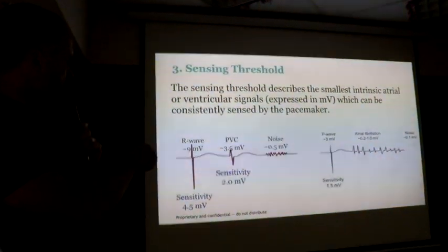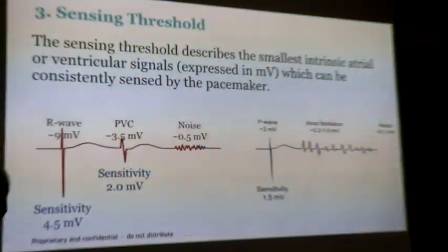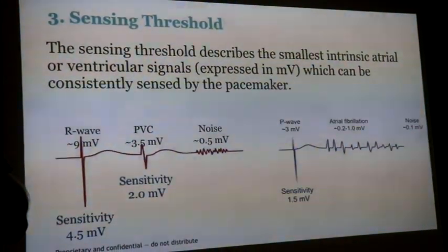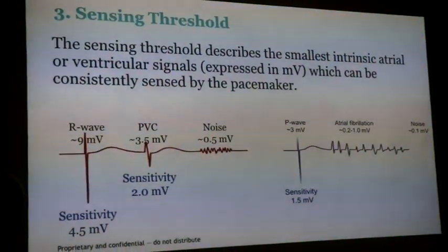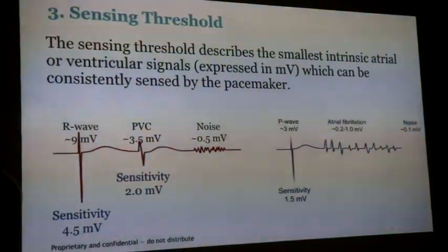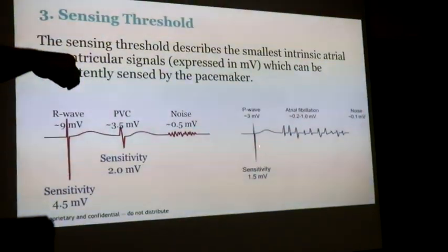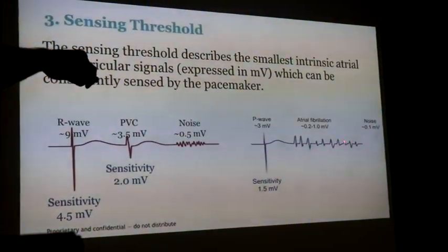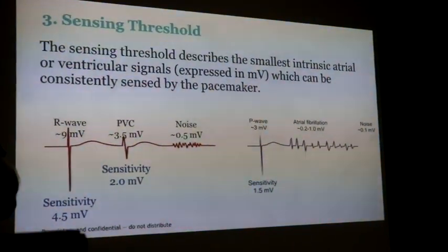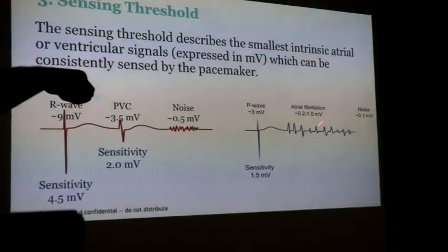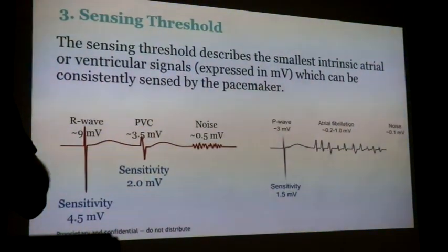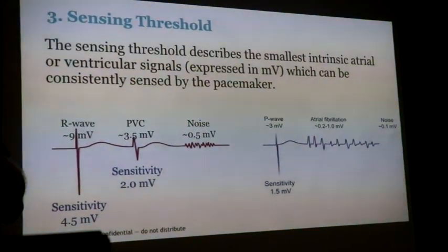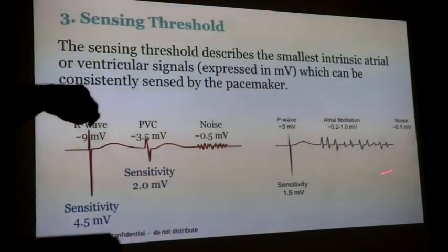So, sensing threshold. Normally we'd set the sensing threshold at around 2.5 millivolts or 2 millivolts for the pacemaker's right ventricular lead. For the atrial lead it's more difficult, because the P wave might be this big, but the P wave in AF might be a lot smaller. And you want to pick this up because you want to know if your patient is having AF, so he might be at risk of stroke. So we need to pick this up here.